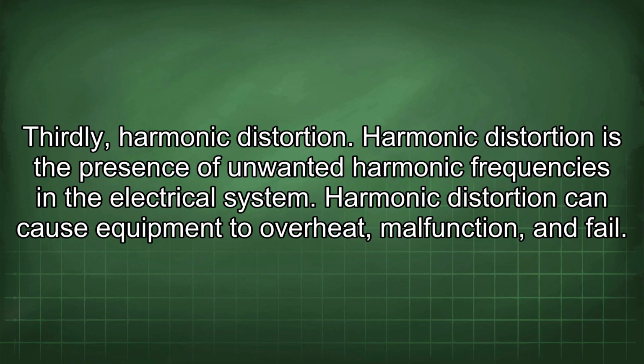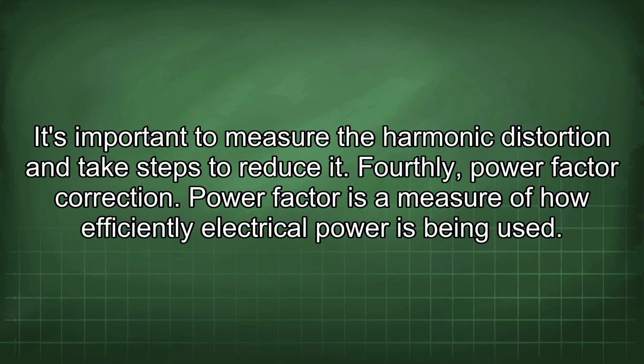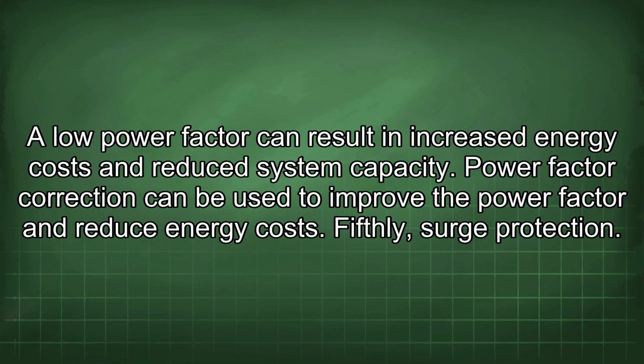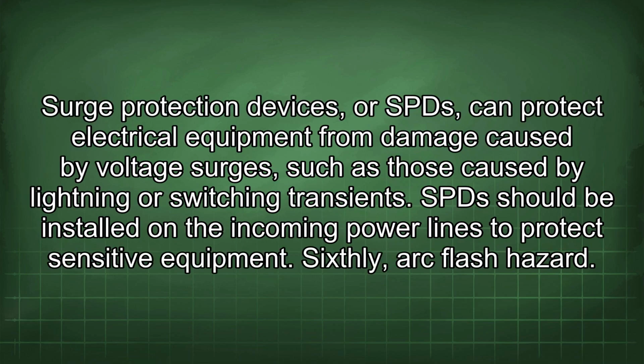Thirdly, harmonic distortion. Harmonic distortion is the presence of unwanted harmonic frequencies in the electrical system. Harmonic distortion can cause equipment to overheat, malfunction, and fail. It's important to measure the harmonic distortion and take steps to reduce it. Fourthly, power factor correction. Power factor is a measure of how efficiently electrical power is being used. A low power factor can result in increased energy costs and reduced system capacity. Power factor correction can be used to improve the power factor and reduce energy costs. Fifthly, surge protection. Surge protection devices, or SPDs, can protect electrical equipment from damage caused by voltage surges, such as those caused by lightning or switching transients. SPDs should be installed on the incoming power lines to protect sensitive equipment.